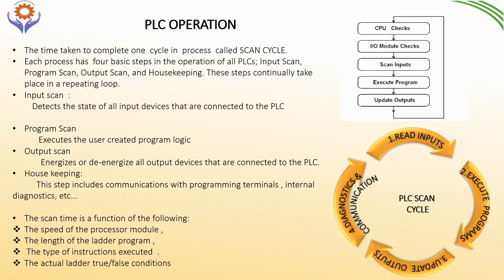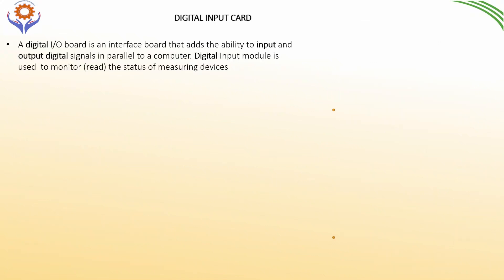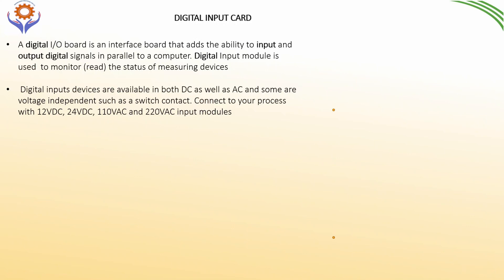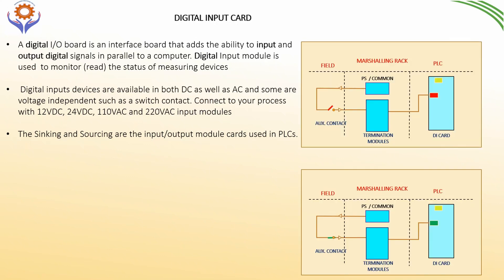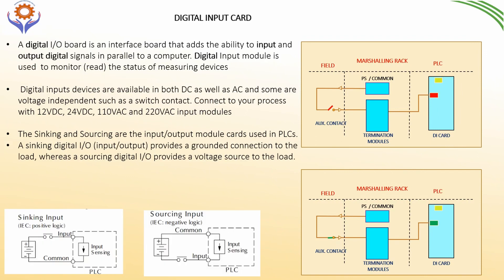What is the digital input/output board? It is an interface board that adds the ability to input and output digital signals in parallel to the PLC. The digital input module is used to monitor the status of measuring devices. Digital input devices are available in both DC and AC, and some are voltage-independent such as switch contacts. They connect to your process with 12V DC, 24V, 110V AC, and 220V AC input modules. There are two types of input modules in PLCs: source and sink input modules. In source input, common is connected with positive voltage and negative with input signals. In sink inputs, it is vice versa — common is connected with negative voltage and positive is connected with the input devices.